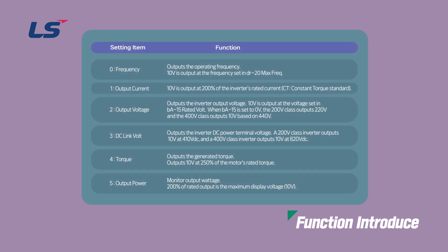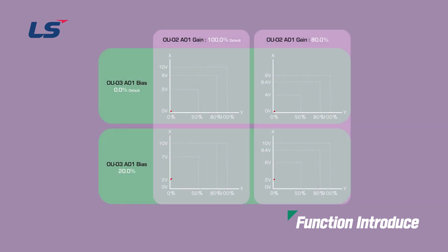The same applies to analog output. Various AC drive operation information such as output frequency and output current can be converted to voltage or current and output through analog output terminals such as the AO terminal. You can also adjust the size of the actual output voltage or current according to the output value.